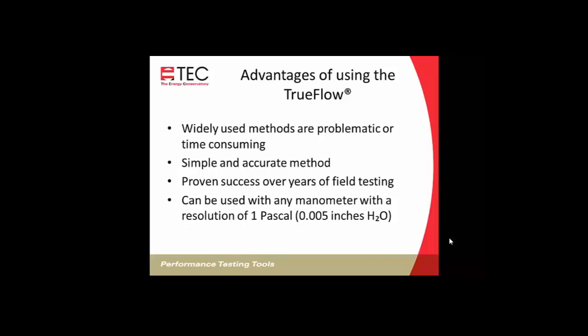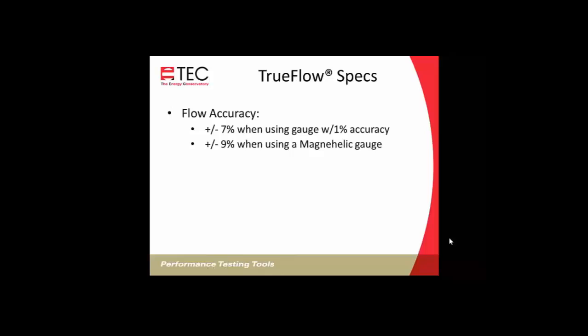It can be used with any manometer with a resolution of 1 Pascal. Those of you that are using inches of water, it's 0.005 inches of water. The DG700 has a resolution of 1/10 of a Pascal, but you can use a pressure gauge with a resolution of at least 1 Pascal. Flow accuracies, plus or minus 7% when you're using a gauge that has a 1% accuracy. Or if you're using the magnehelic gauge, you'll have about plus or minus 9% accuracy.